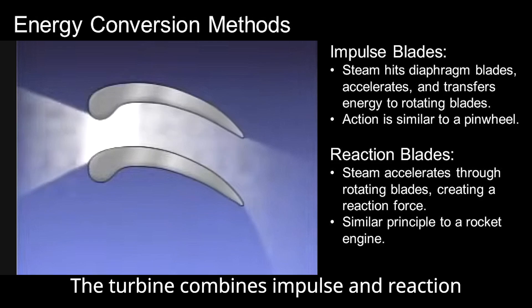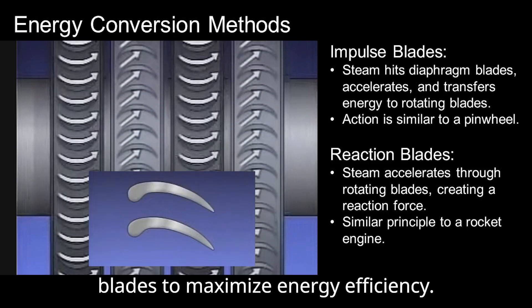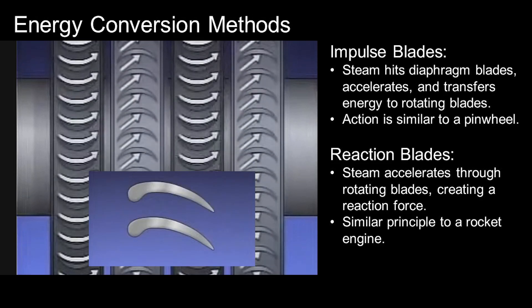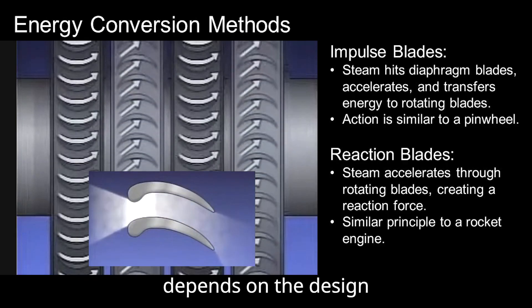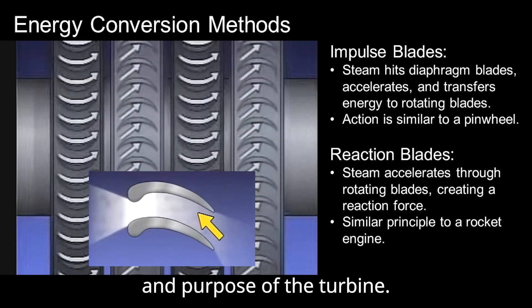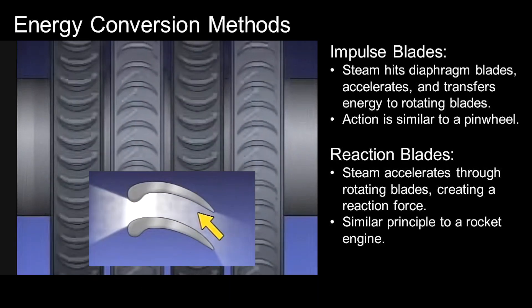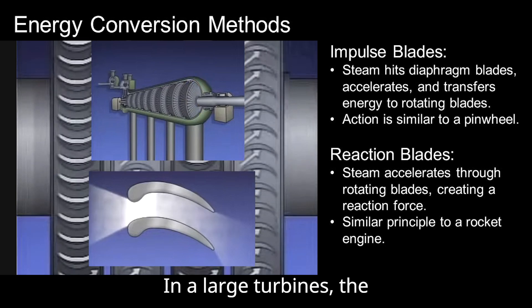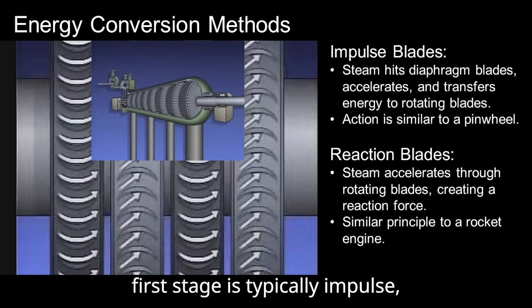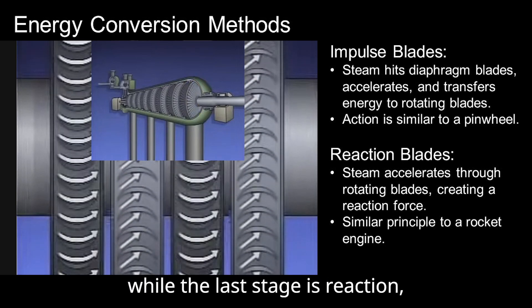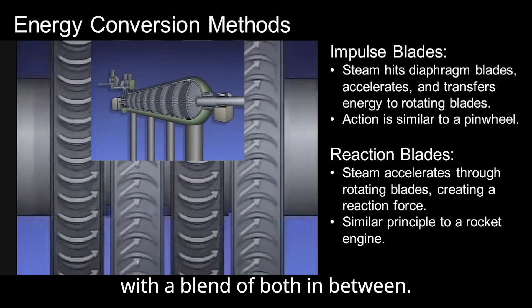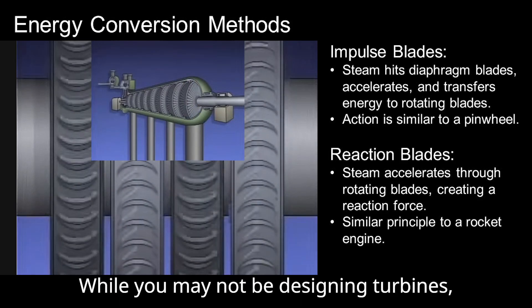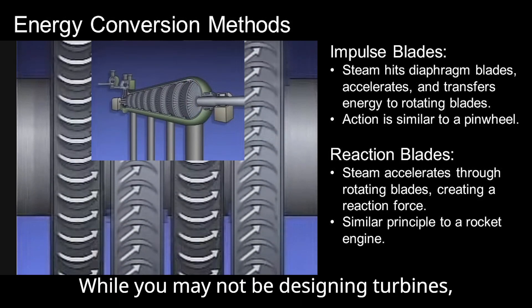The turbine combines impulse and reaction blades to maximize energy efficiency. The proportion of each type of blade depends on the design and purpose of the turbine. In a large turbine, the first stage is typically impulse, while the last stage is reaction, with a blend of both in between.